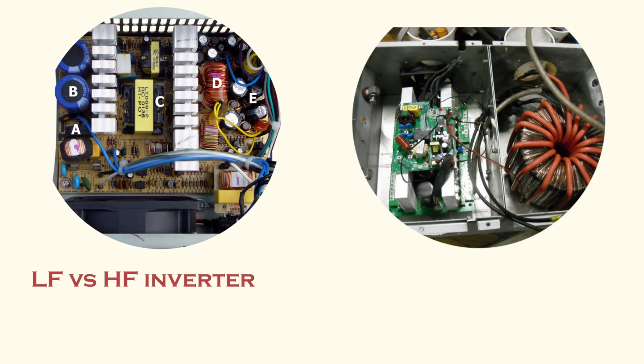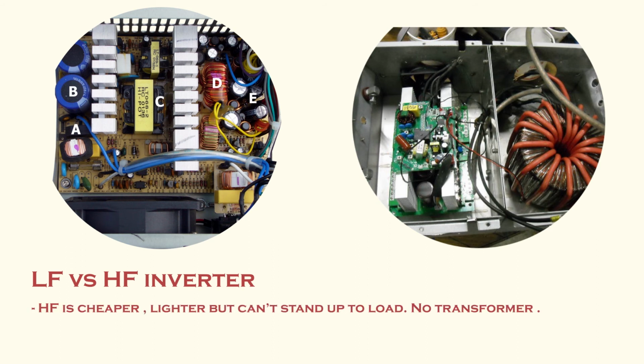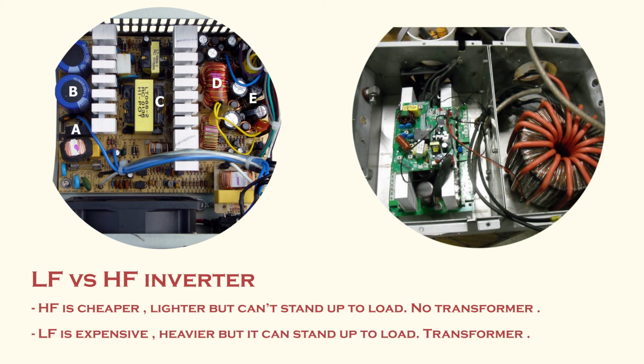The other terminology I want to cover is low frequency and high frequency inverters. Most plug-and-play inverters, around 5,000 to 8,000 watts, are high frequency. They're usually cheaper and lighter, but can't stand up to higher loads because there's no transformer. Low frequency inverters are more expensive and heavier because they have a transformer built in, and they can handle high loads.